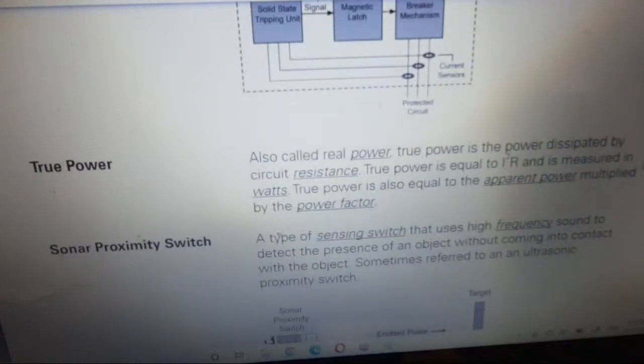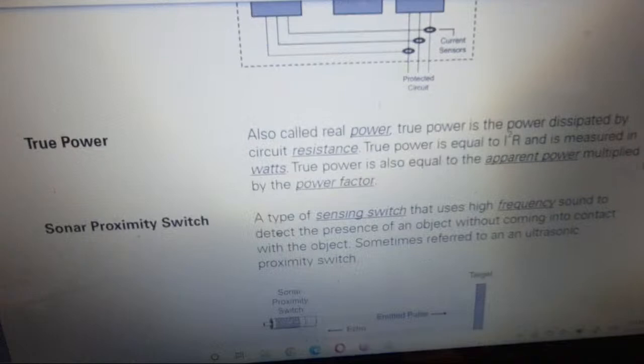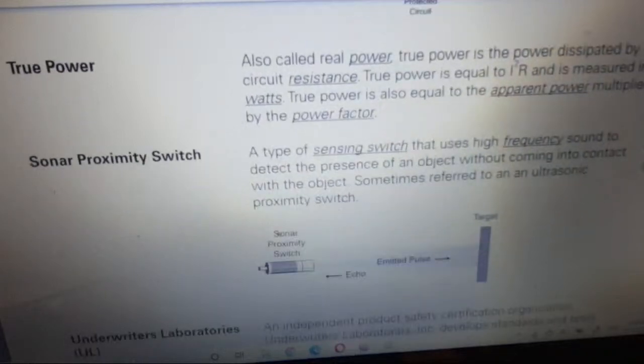True power, also called real power. True power is the power dissipated by circuit resistance. True power is equal to current squared times resistance, or I squared R, and is measured in watts. True power is equal to the apparent power multiplied by the power factor. Sonar proximity switch, a type of sensing switch that uses high frequency sound to detect the presence of an object without coming into contact with the object, sometimes referred to as an ultrasonic proximity switch.